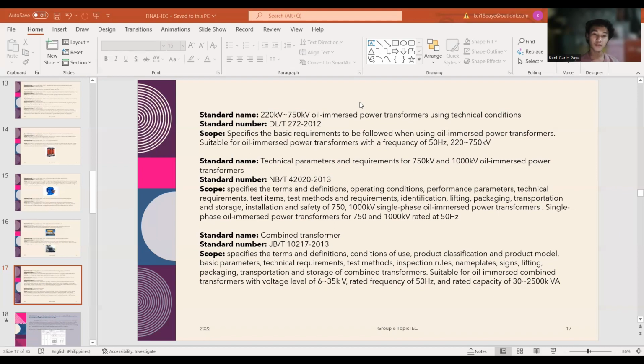And lastly, the combined transformer. So this combined transformer standard specifies the terms and definitions, conditions of use, product classifications and product model, basic parameters, technical requirements and test methods, inspection rules, nameplates, signs, lifting, packaging, transportation, and storage of combined transformers, suitable for oil immersed combined transformers with voltage level of 6 to 35 kilovolts, rated frequency of 50 Hz, and rated capacity of 30 to 2500 kilovolt-amperes.